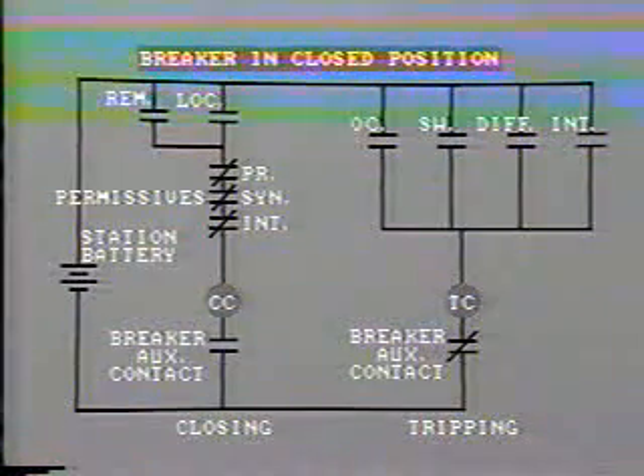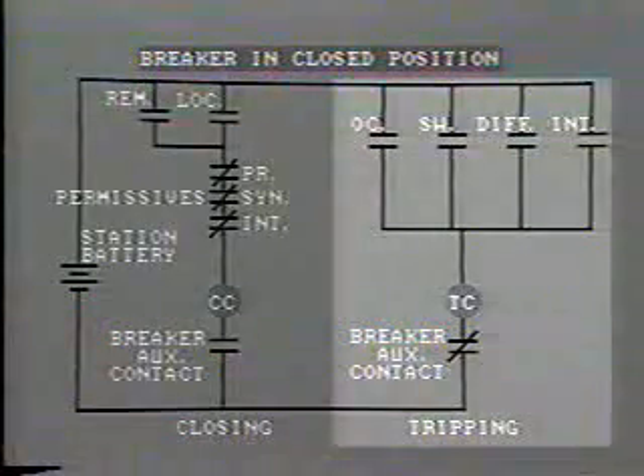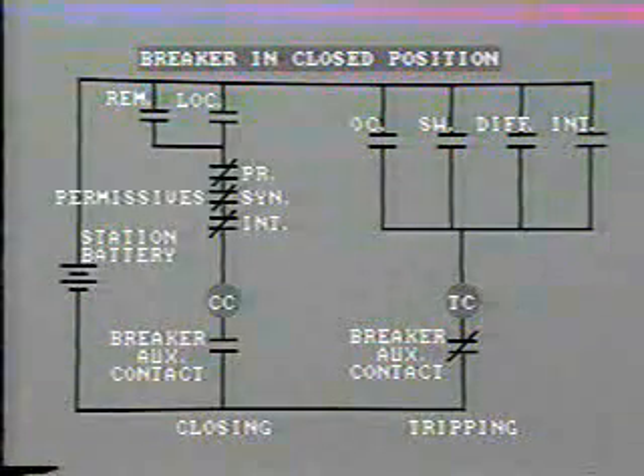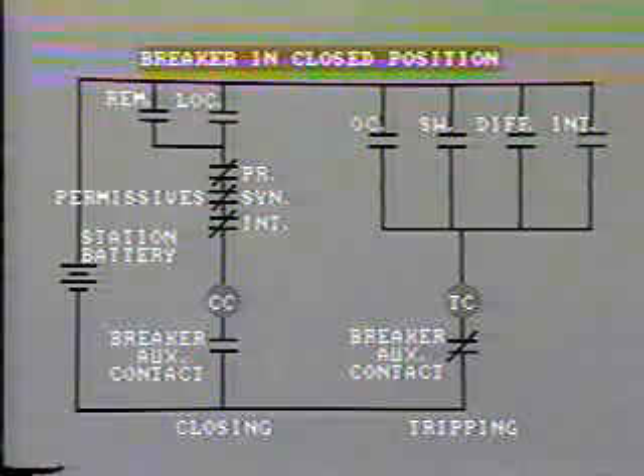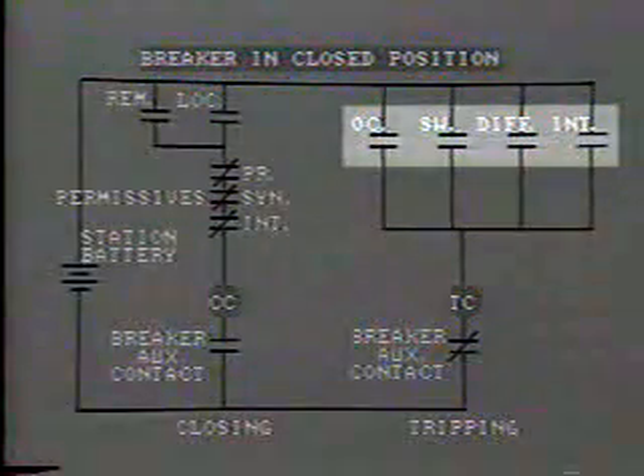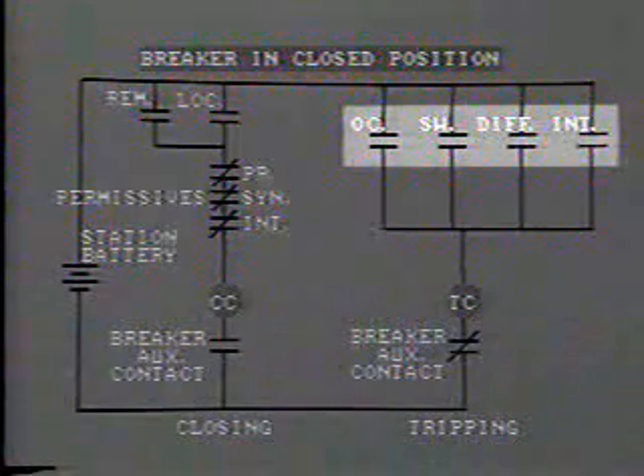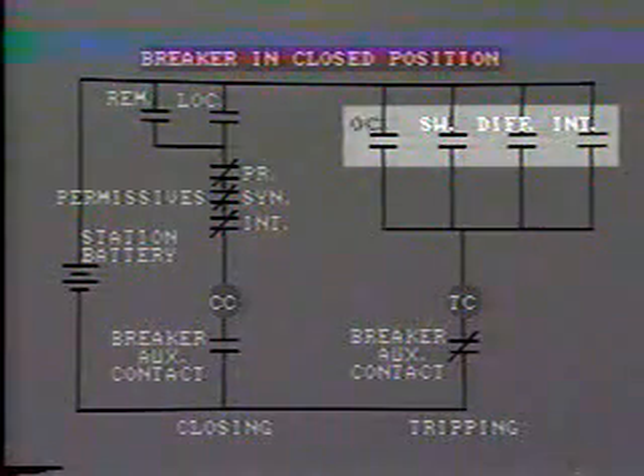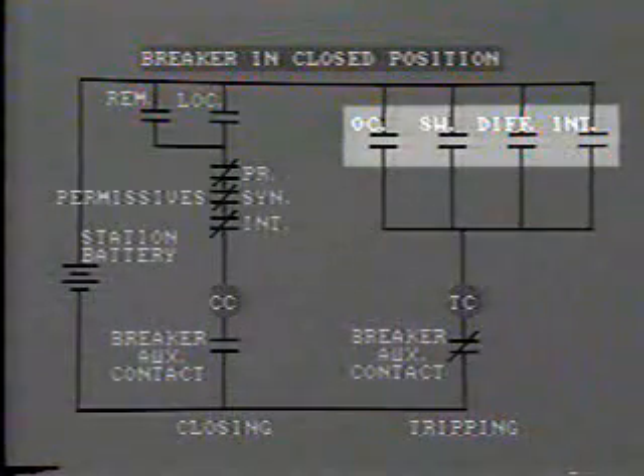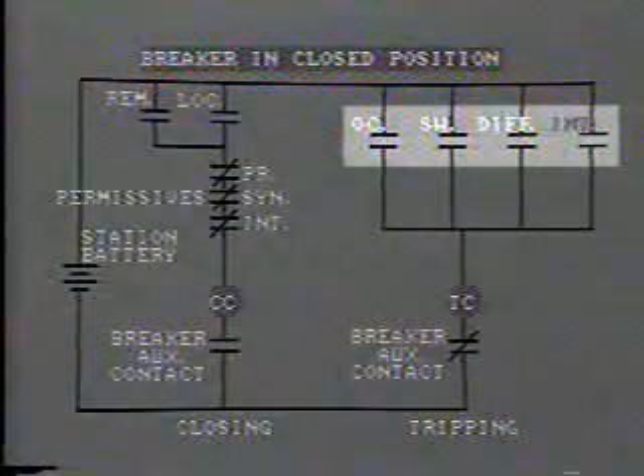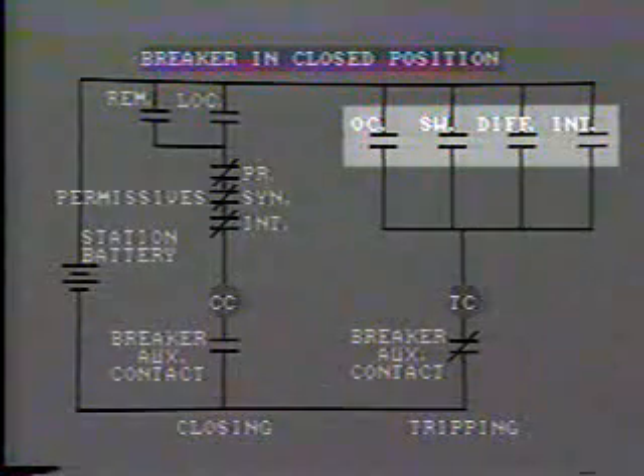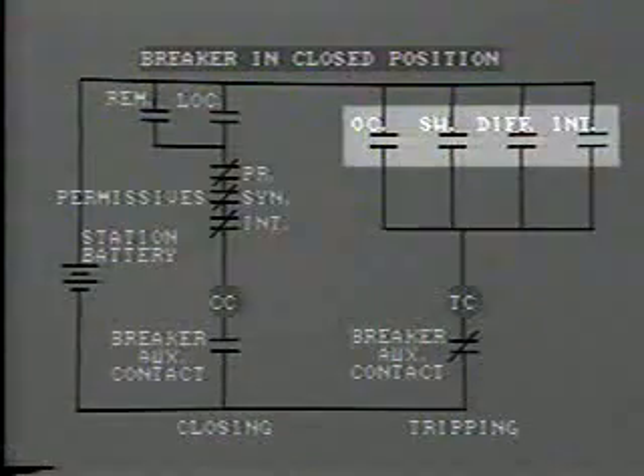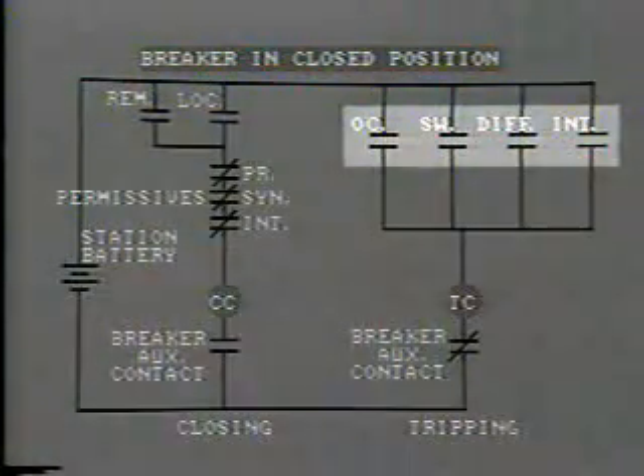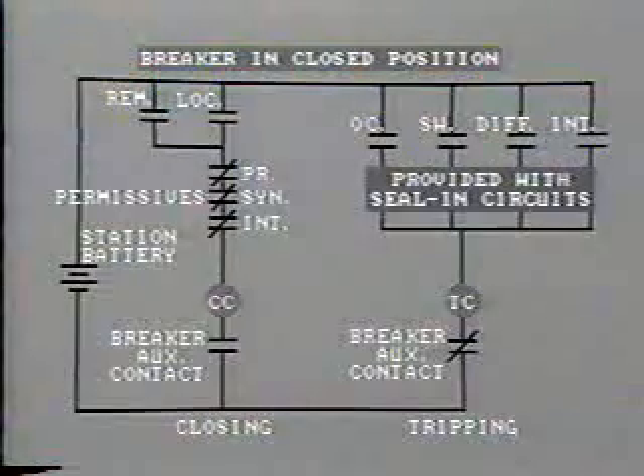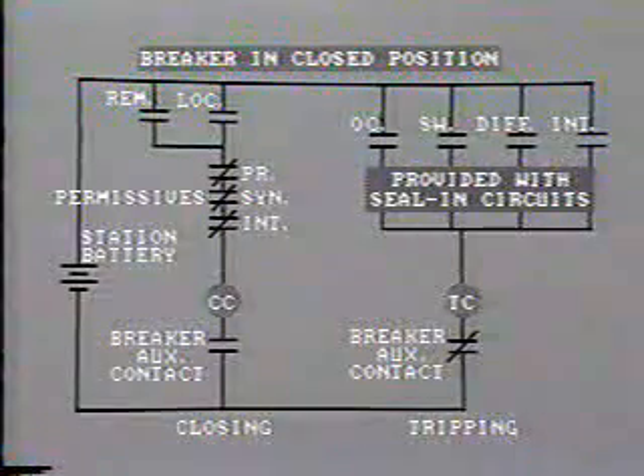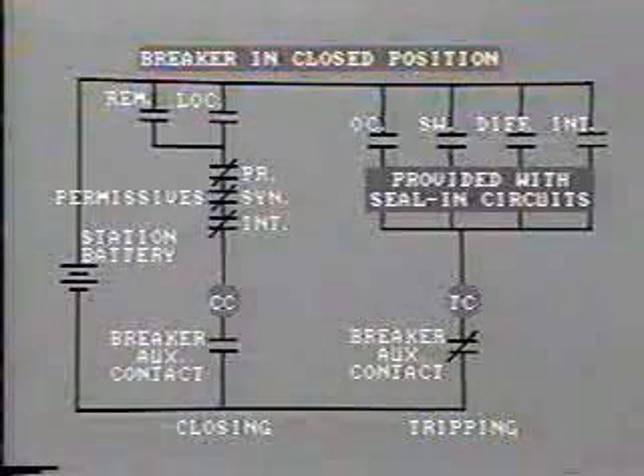To trip the breaker open, the tripping circuit must be energized. In the case of a tripping circuit, instead of permissive contacts in series, we'll find several pairs of contacts in parallel. Look at these tripping contacts. Overcurrent relay, manual switching, differential relay, remote intertrip. Closing any one of these pairs will energize the tripping circuit and open the circuit breaker. Often these tripping contacts are provided with seal-in circuits, as we discussed in the previous segment.